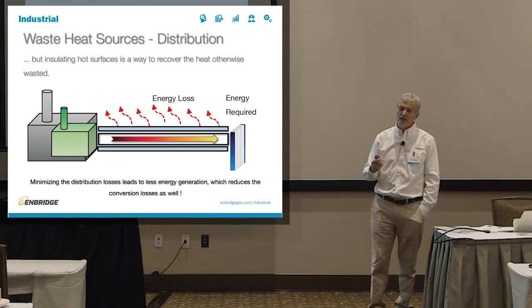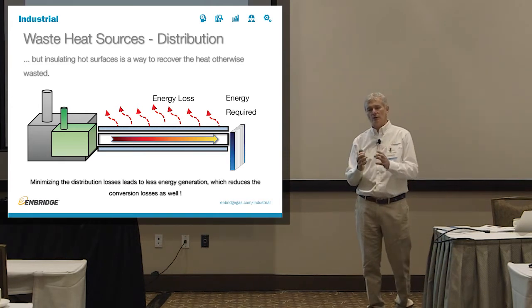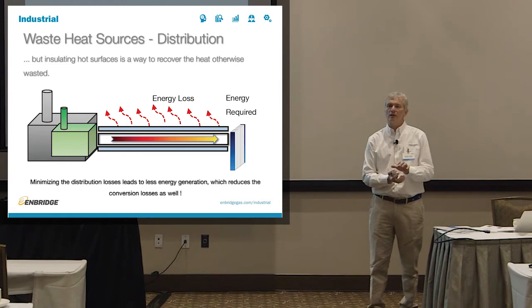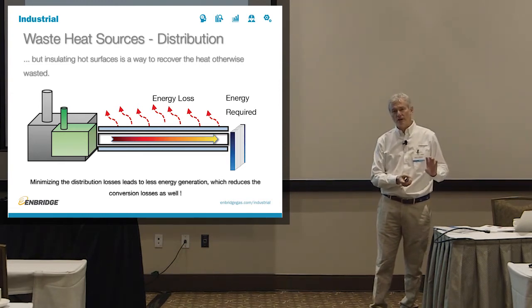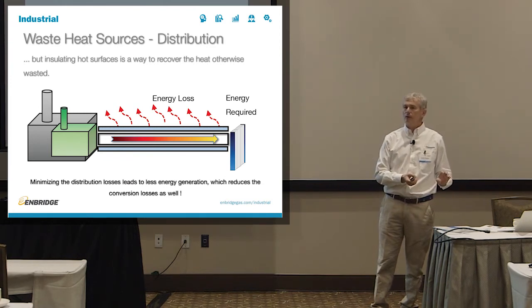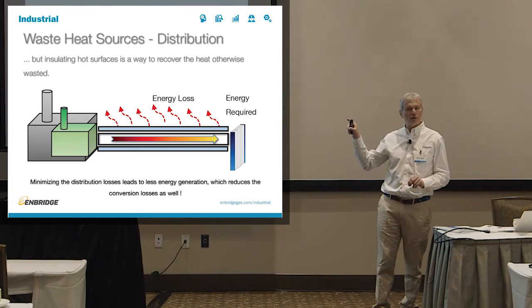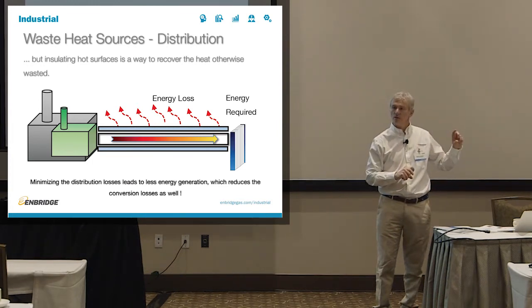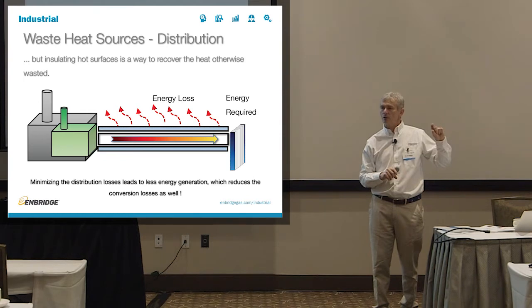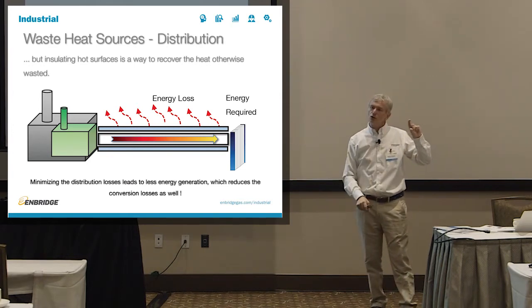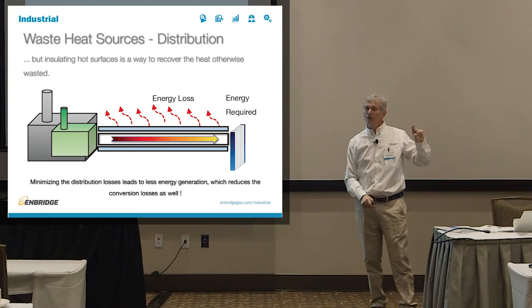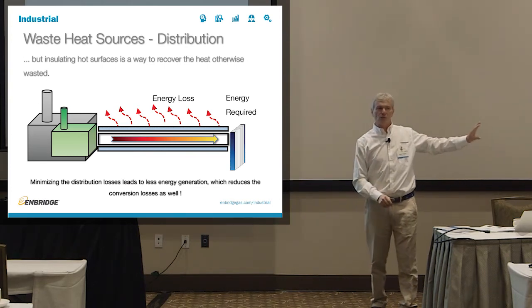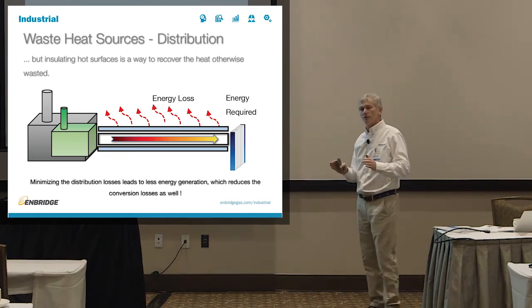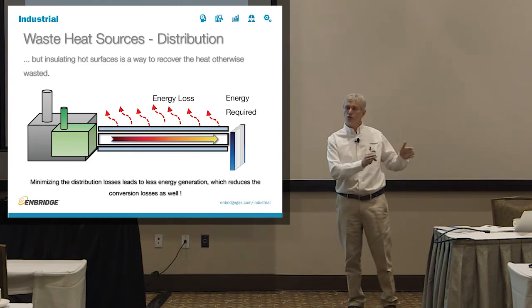So even though, in traditional terms, this is not necessarily what we think of as heat recovery, you are recovering the losses that would otherwise incur, which would then require your energy generation to be less. And you have to remember, the less energy you generate, the less of those conversion losses you will incur as well. If you need to generate 100 horsepower out of your boiler and you lose 20%, you're losing 20 horsepower. If you only need an 80 horsepower boiler because you saved on the energy distribution losses, now you only are going to lose 20% of 80 horsepower. So you're saving all the way at the back, not just in these distribution losses. So reduction in distribution losses also reduces the conversion losses.